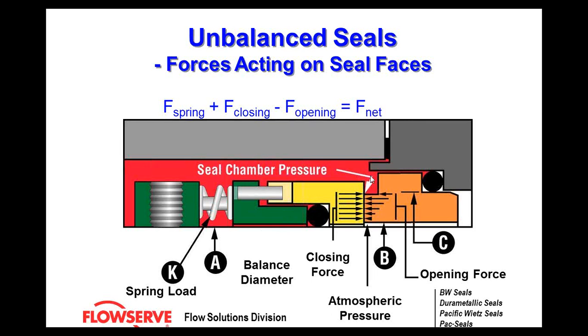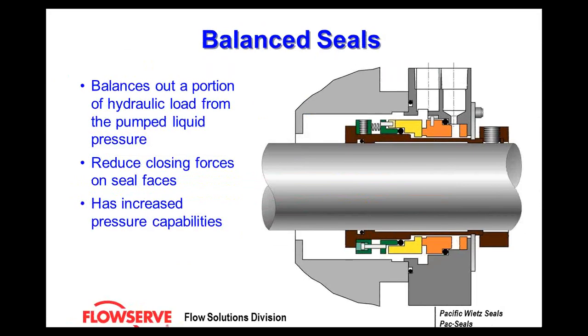The seal chamber pressure also acts to open the two faces and provide the lubrication needed to operate the mechanical seal — it starts at a higher pressure in the seal chamber and drops toward atmospheric on the other side. A balanced seal balances out a portion of the hydraulic loads from the pump liquid pressure, reducing the closing forces on the seals and providing increased pressure capabilities. Balanced seals allow you to engineer the desired leakage and are the most common in API applications; most high-end pumps will have balanced seals.